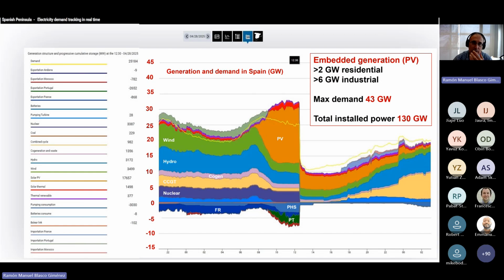I'm going to let you know a little bit about the characteristics of the Spanish system prior to the blackout. The Spanish and Portuguese systems have been operated at about 60–70% PV plus wind almost every day, and that doesn't match quite well with, for example, what our colleagues in Denmark are doing. But in our case, we don't have the ability to export to Norway or to Sweden or to Germany, so they have a much better connection. Our maximum demand is 43 gigawatts. We have 130 gigawatts total installed power, of which 8 gigawatts are embedded PV, residential and industrial. Before the blackout, we had some 25% PV.